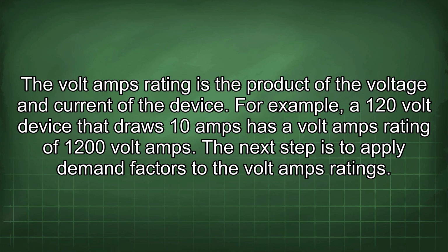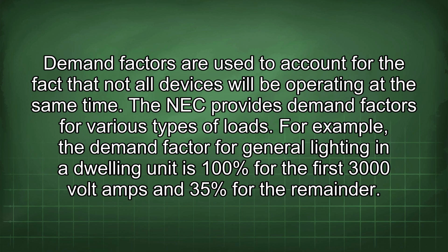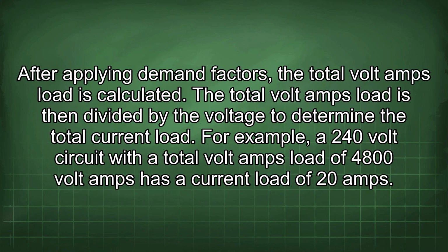The next step is to apply demand factors to the volt-amps ratings. Demand factors are used to account for the fact that not all devices will be operating at the same time. The NEC provides demand factors for various types of loads. For example, the demand factor for general lighting in a dwelling unit is 100% for the first 3000 volt-amps and 35% for the remainder. After applying demand factors, the total volt-amps load is calculated. The total volt-amps load is then divided by the voltage to determine the total current load. For example, a 240-volt circuit with a total volt-amps load of 4800 volt-amps has a current load of 20 amps.